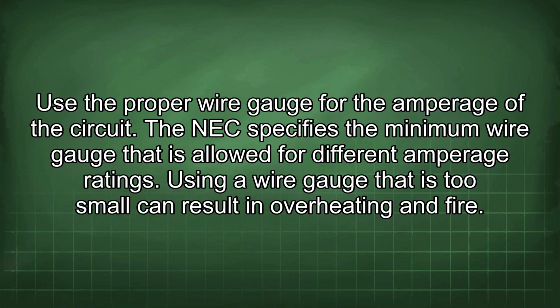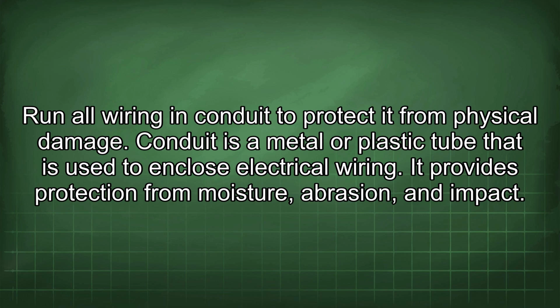Use the proper wire gauge for the amperage of the circuit. The NEC specifies the minimum wire gauge that is allowed for different amperage ratings. Using a wire gauge that is too small can result in overheating and fire. Run all wiring in conduit to protect it from physical damage.